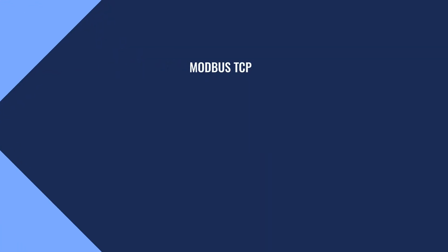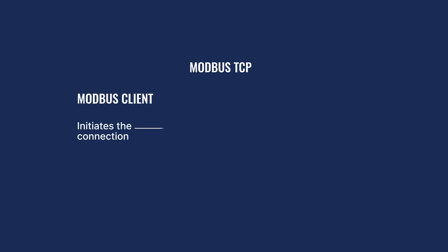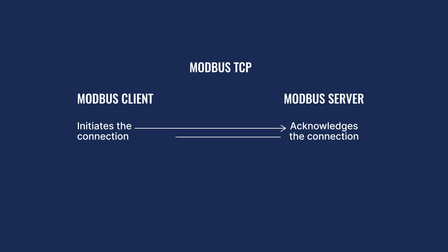Modbus works on a client-server model, which is very similar to Q&A interview sessions. However, the way initial communication is established differs between the TCP and RTU variations. In Modbus TCP, the client initiates communication and waits for an acknowledgement from the Modbus server. If the server does not respond, the end device gets a timeout.